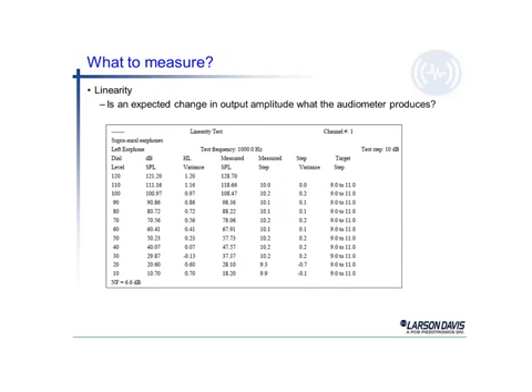Linearity is another test we like to do on the audiometer. This one shows a measured step of 10 decibels. Ideally, if we change that attenuation by 10 dB and come down 10 dB, it should track. It should track 10 dB for each step, and we can see a variance of a few tenths of a dB as we go down in level. Again, very well within the target, a step of somewhere between 9 to 11 dB is acceptable for an audiometer.